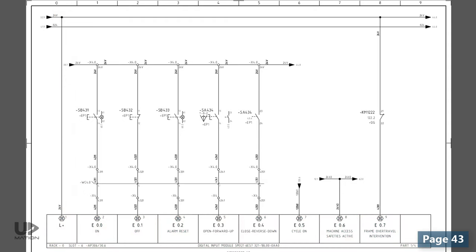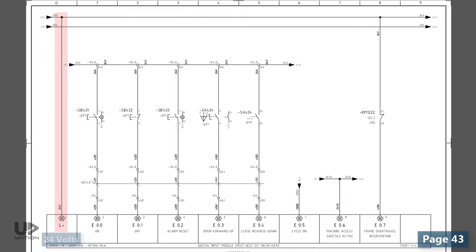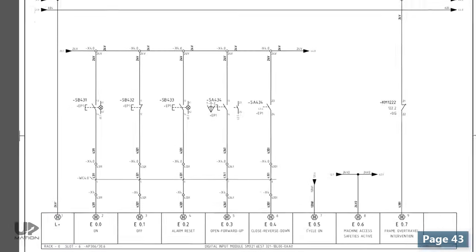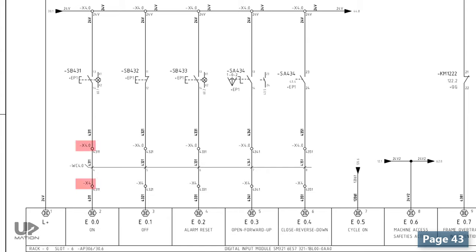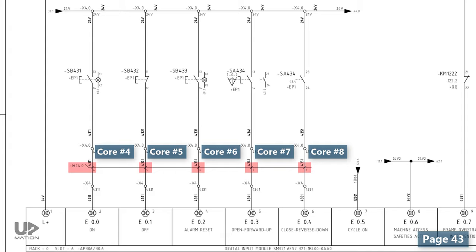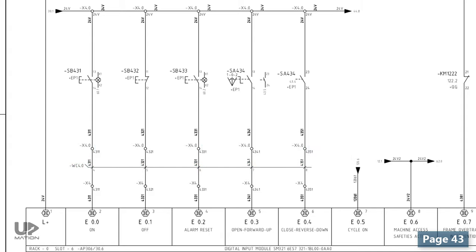Same as before, the 24V power is connected to the corresponding terminals of the card. The first signal from the left comes off a push button tagged as SB431. The X4 terminal block and the core number 4 of the WC4.0 cable, which is a multi-core cable, are in between the push button and the card.